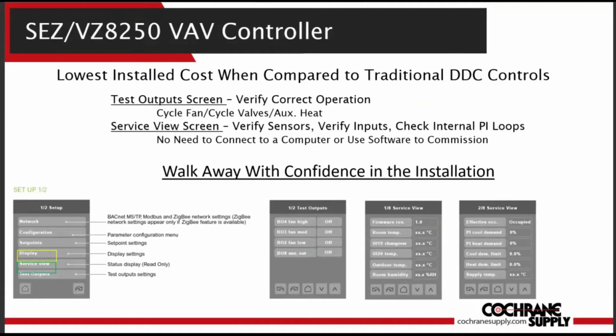Test outputs will verify wiring and operation for the dampers, fan, and reheat, kind of like a hand-off-auto switch. Electricians and technicians can use this to verify correct wiring to the outputs has been performed. There's no need to fake out the controller by changing set points to force heating or cooling operations to begin. After a 2-minute timeout or navigating to other 8250 screens, the unit will be set back to the proper outputs. You don't have to worry about leaving any setting in override. Knowing that the unit is functioning correctly provides confidence that you won't have to revisit the unit to make wiring corrections.